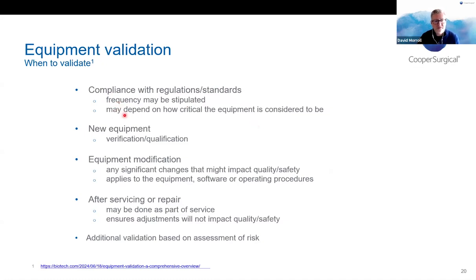And the frequency of that revalidation probably depends on how critical the equipment is. So, for example, we know how important incubators are to IVF labs. That inevitably will potentially lead to revalidation more commonly than some other less important pieces of equipment. You'll certainly be required to validate new equipment when it comes into the lab, because you want to know for sure that it's performing appropriately. And then you will also revalidate or validate if equipment is modified. When we say modification, we're really talking about any significant changes that might impact safety or quality. So anything that might significantly affect what we're doing needs to be retested.